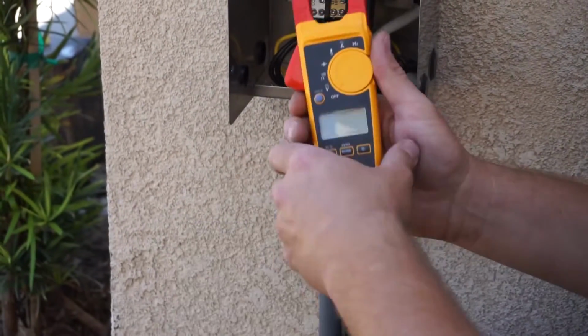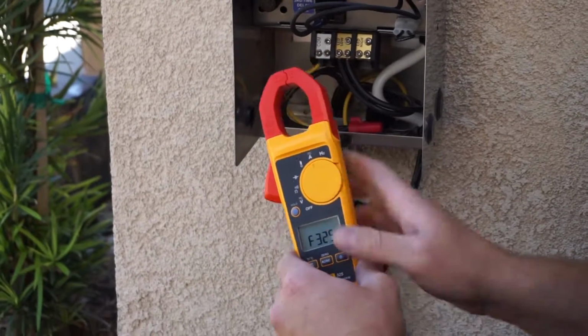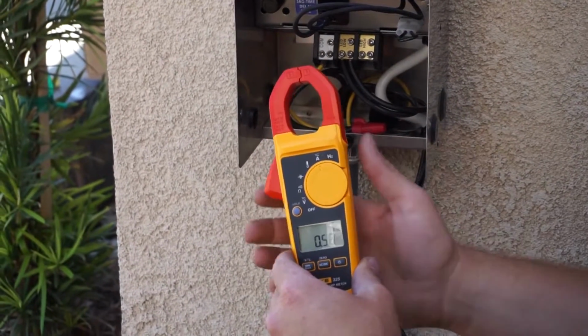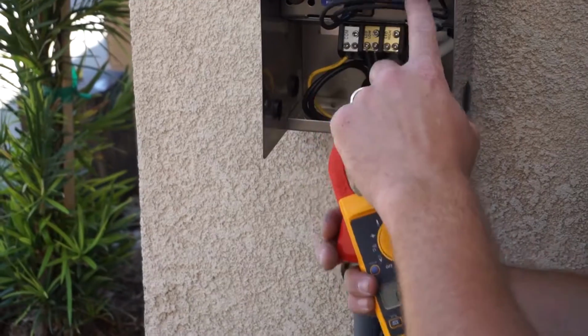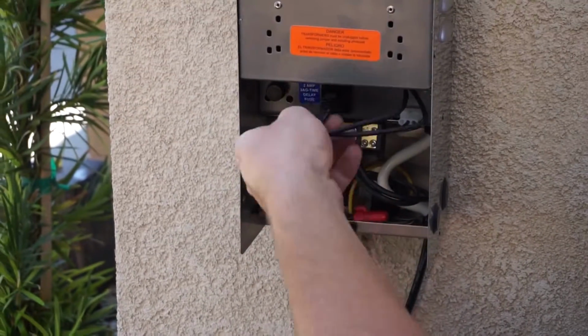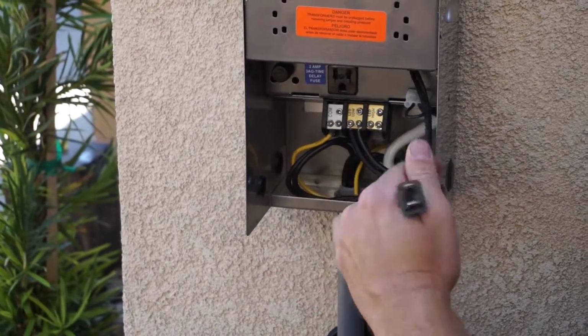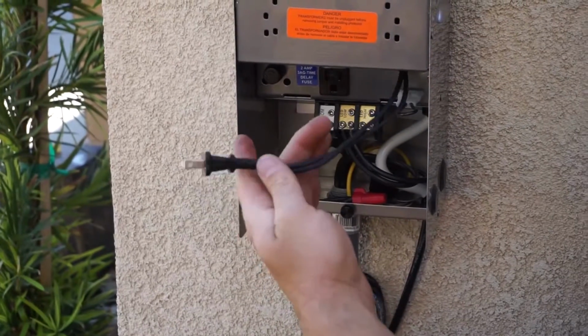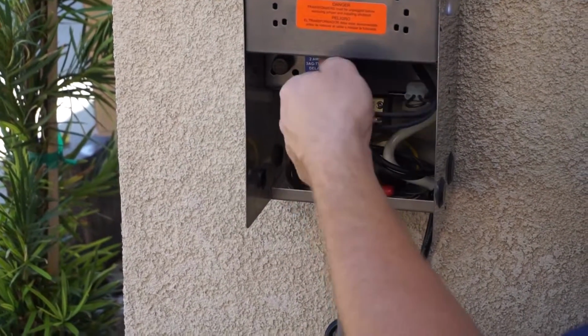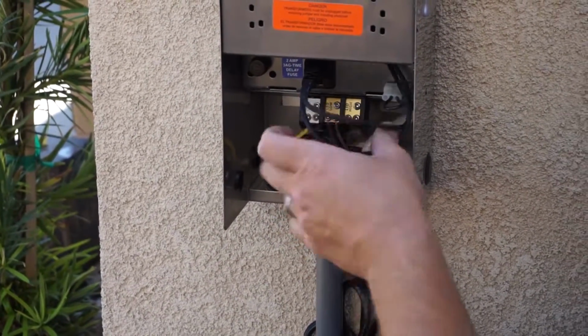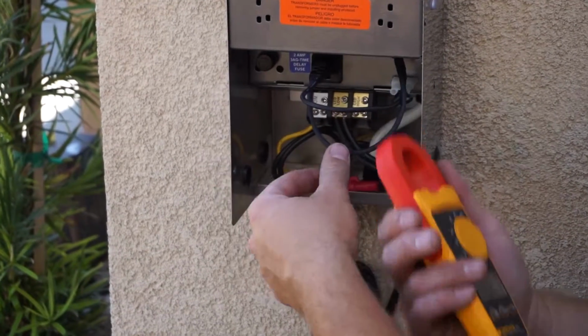So I'm going to take my amp probe to check my primary amps, set on my amp setting. I'm going to let this zero out. And then if you notice our primary power connection right here, we have a fused outlet. This is the power cord that actually goes to the transformer itself. So when you plug it in, this is separate because when you check amperage, you have to check either the hot or the common side.